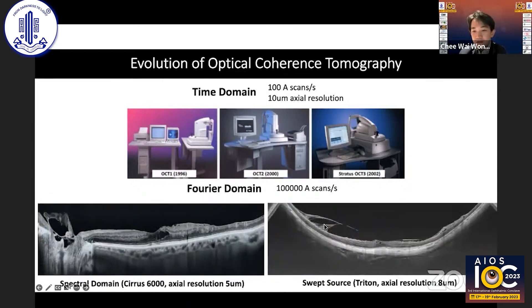OCT has undergone a lot of improvements over the past three decades. The first time-domain OCTs in the 1990s could only manage 100 scans per second at 10 microns axial resolution. It wasn't until the early 2000s with the Stratus OCT that the modality gained more traction. Today, Fourier domain OCTs — both spectral domain and swept source — are capable of 1000 times the scan speed at much higher axial resolution.